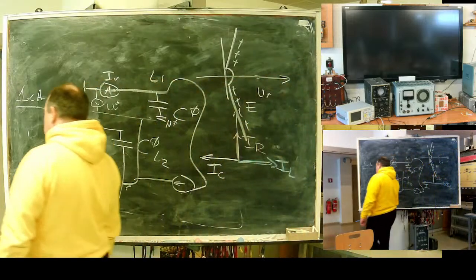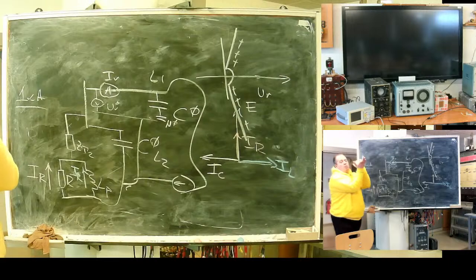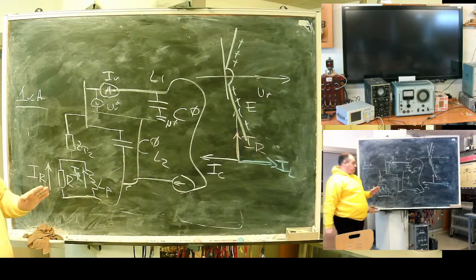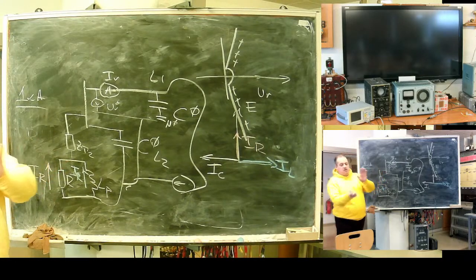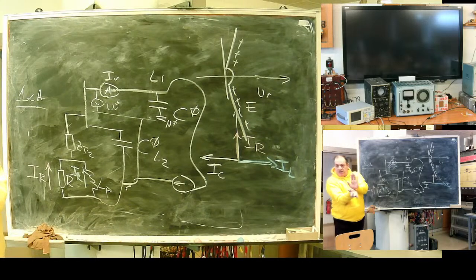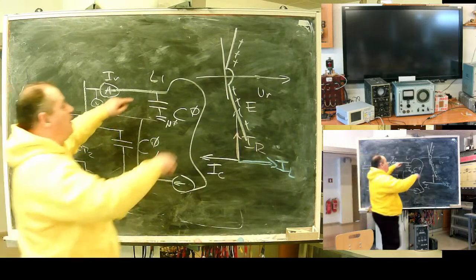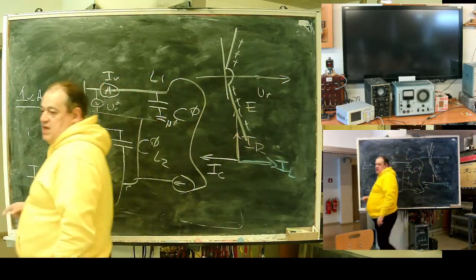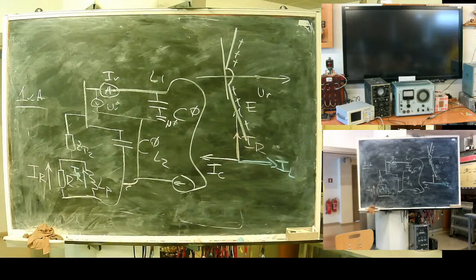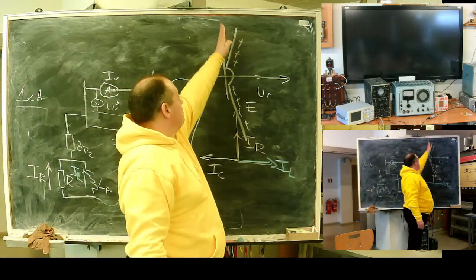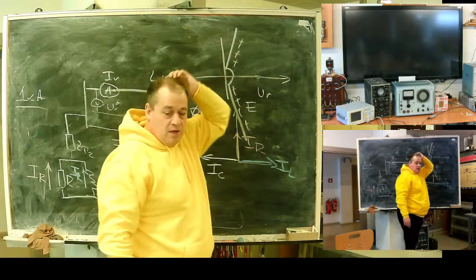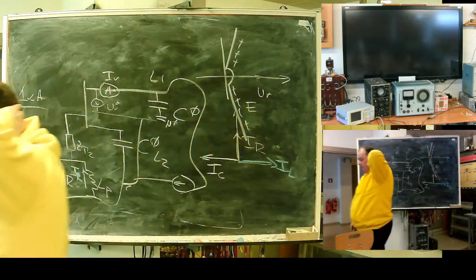Isolated and low ohm neutral protection characteristics are not compatible. In case of isolated neutral, you need the opening looking upwards. In case of low ohm resistance, you need the opening looking right. Isolated neutral will not operate in case of low ohm. Low ohm, very questionable. Most probably it will not operate because isolated will be outside. These two characteristics are not compatible.